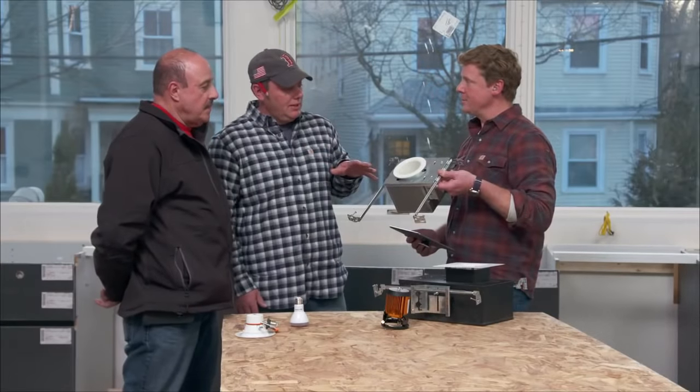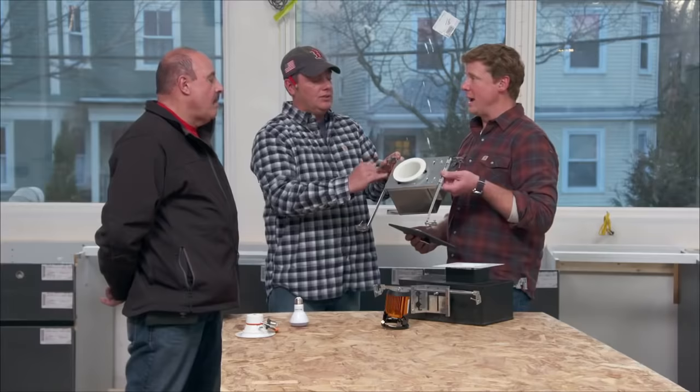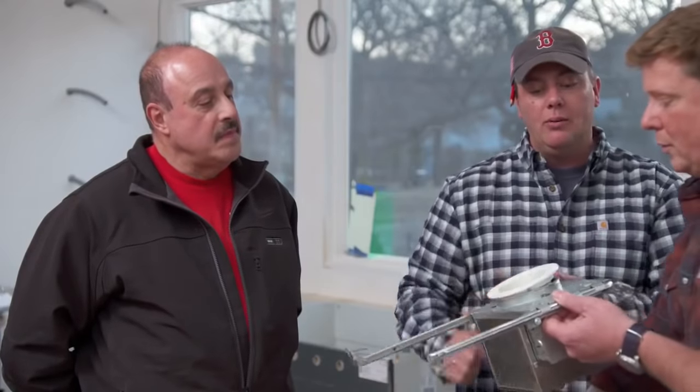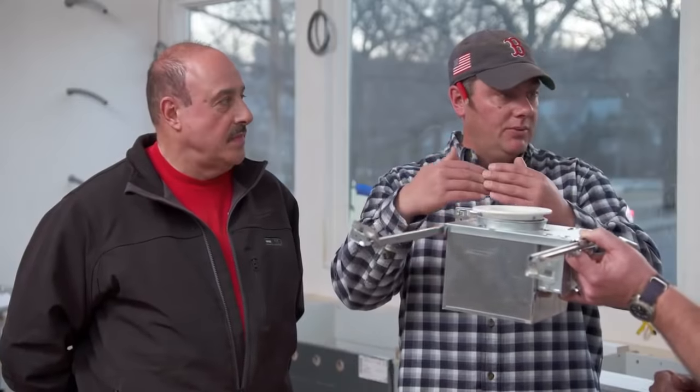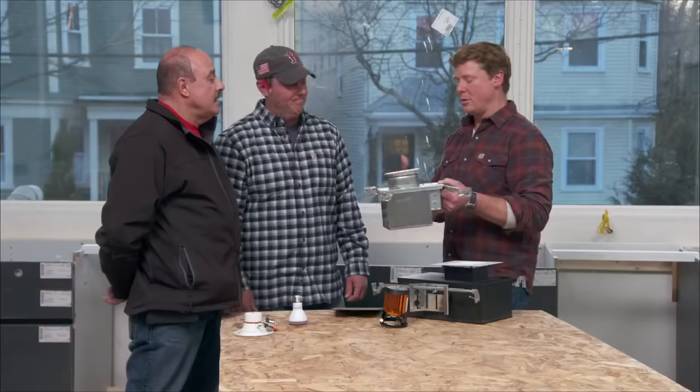Allison on YouTube asks how the housing is fine-tuned for layout with the conventional recessed can. It's simpler than the square flush unit: you set the face of the can even with the backside of the drywall finish, and it sets itself. The can has a built-in half-inch ring already sized for blueboard or drywall. There's a little play if needed, and worst case if the unit is set too high, this particular unit does let you adjust it down after the fact.